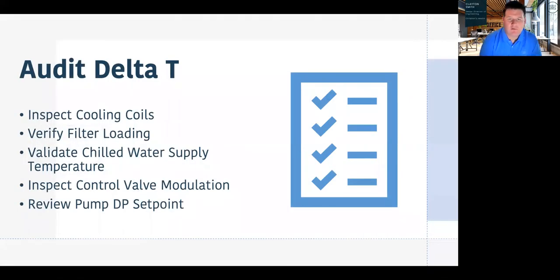So a lot of what I'm going to talk about is very similar to what John and Craig talked about, but from an owner and operator's perspective. Everything in our world from a chiller plant is driven by the delta T, and we want to make sure that we audit that delta T and stay on top of it regularly. If you get a reduced delta T, we go through a checklist of things to find the culprit. First, inspecting our cooling coils.